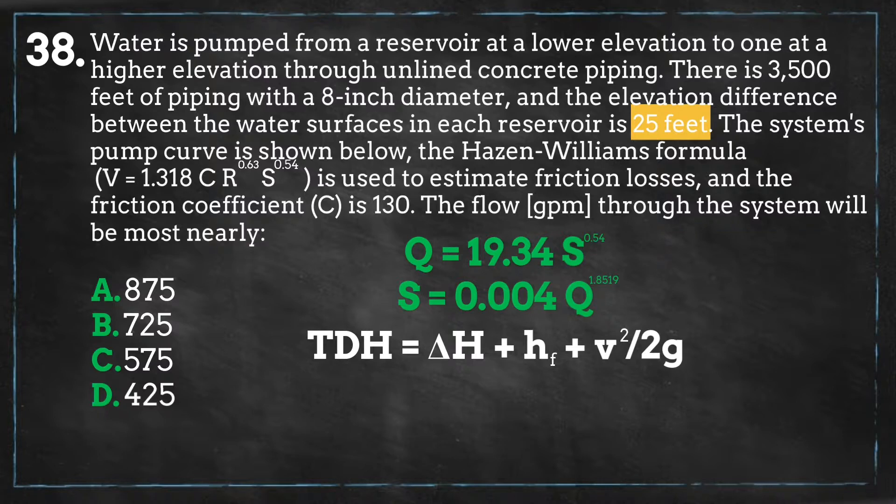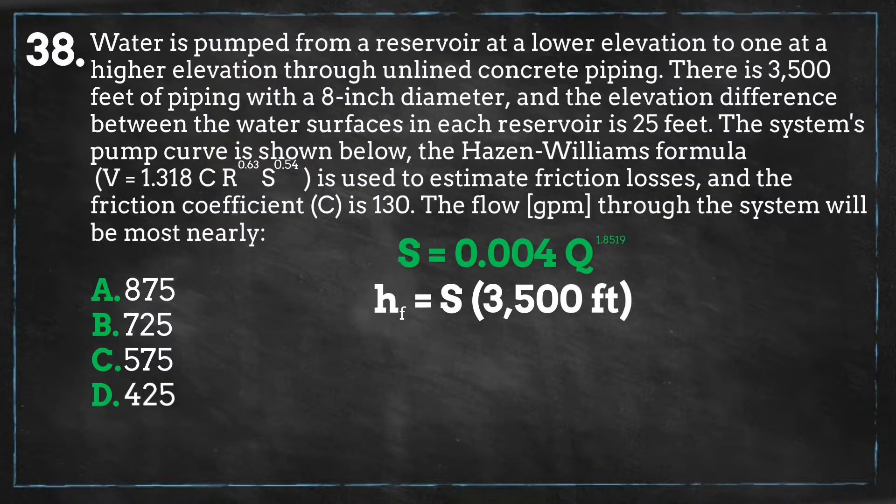Delta H equals 25 feet across the system. We can solve for the velocity at given flow rates, and the slope equation, S equals H sub F divided by L, can be manipulated to solve for H sub F, which equals the slope times the pipe length. Therefore, we will multiply the length of our piping by our equation equaling the slope to get the head loss of that specific flow rate.